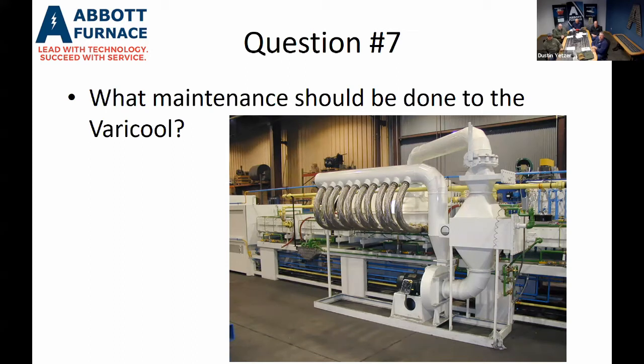Some of the maintenance that needs done on this unit: as you're pulling that hot gas out of that top line, any buildup on your parts, soot, carbon, anything that may be deposited in your furnace or on your parts, is going to act like a vacuum cleaner. It's going to pull that out of the furnace, run it through that filter housing, and it's going to get caught in that heat exchanger. So periodically, anywhere from weekly to monthly, we'll have to pull that filter and clean it. Judging by the condition of the filter, we can determine the time period for when we have to pull that heat exchanger and clean it.